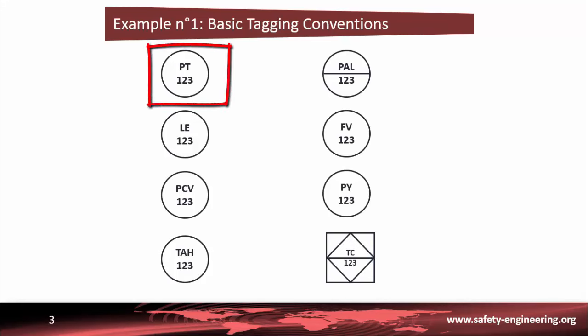PT means a pressure sensor with a transmitter that converts the raw signal at the output of the sensor, the measured value, to a normalized signal from 4 to 20 mA current loop. In general, this signal is transmitted to the controller.